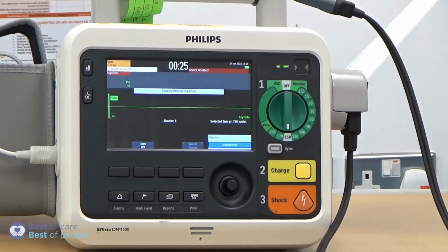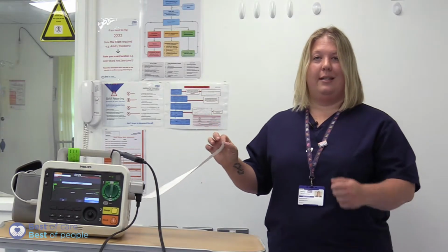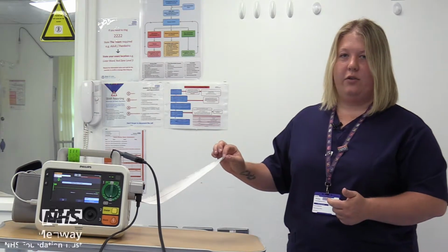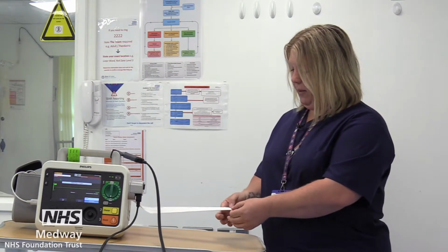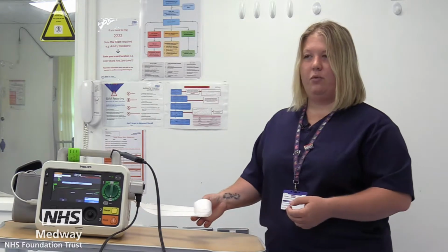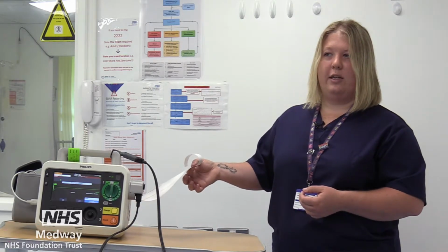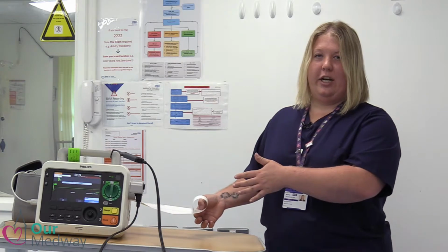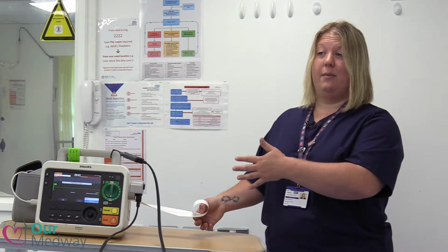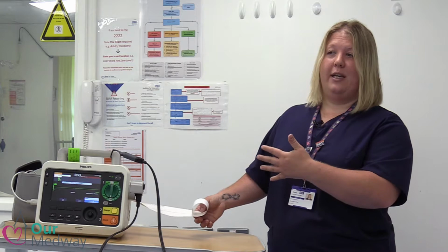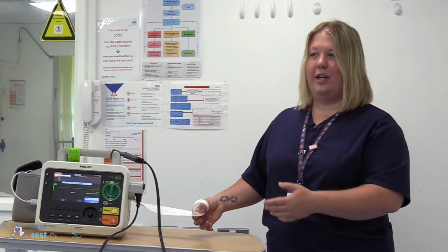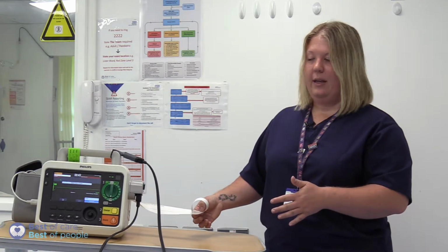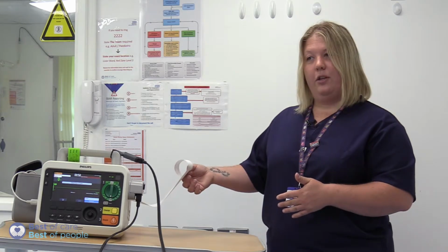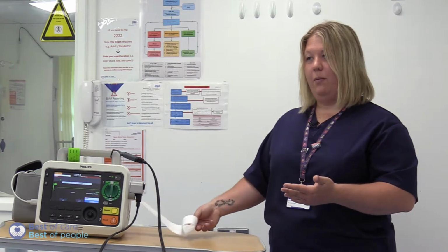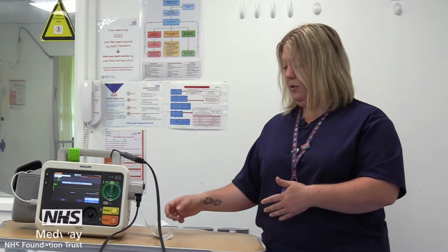And what you'll have on this test strip is the date and time of which you've done your daily check, and it will say that the battery is good, that the defib was able to charge and that a shock was delivered. And essentially that's our daily check, because that's the main function of this. We need to make sure that every day this defib is capable of charging and delivering a shock in its most basic function. I would advocate that you leave this on for the next 24 hours so that anybody who then goes to use this defib knows that it's passed its user test and it's ready.